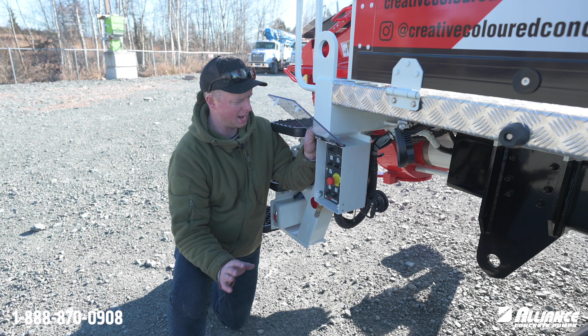So once you're in local mode, you can operate things like pumping, reverse pump, engine RPM. All the other switches in here, there's vibrator that is on, can be operated either in remote or local, as well as the greaser, the cooling fan, and the horn. Also the E-stop can be depressed in either mode. So that's inside this panel.